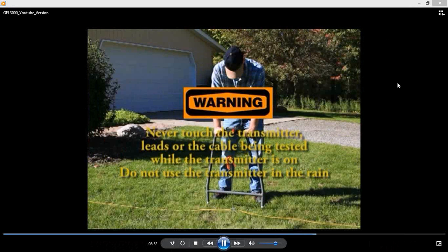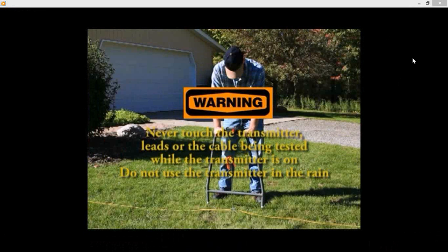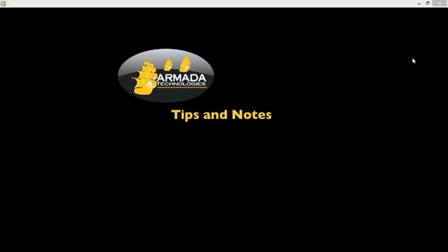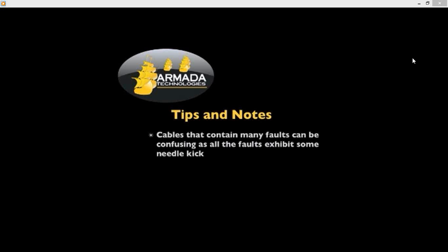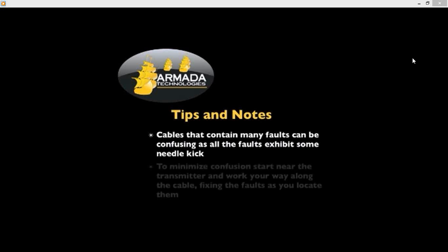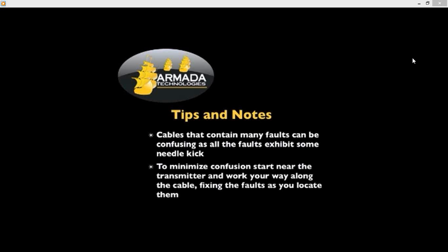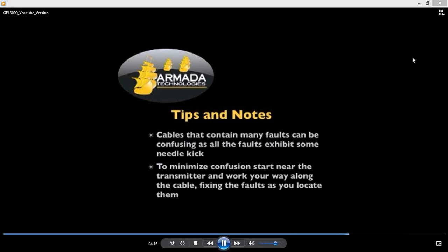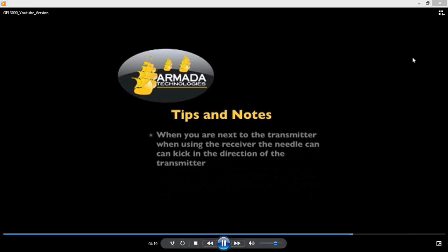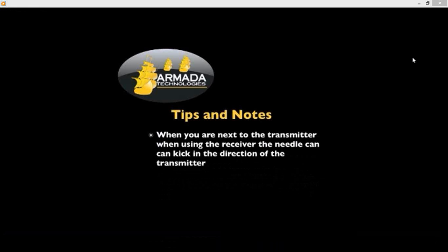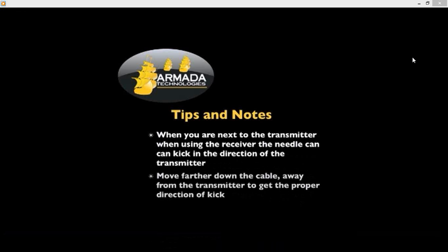Before repair, turn off the transmitter and disconnect it from the cable. Never touch the transmitter, leads, or the cable being tested while the transmitter is on, and do not use the transmitter in the rain. Failure to follow these precautions could lead to injury or death. Cables that contain many faults can be confusing as all the faults exhibit some needle kick. To minimize confusion, start near the transmitter and work your way along the cable, fixing the faults as you locate them. If you are next to the transmitter when using the receiver, the needle can kick in the direction of the transmitter. Move further down the cable, away from the transmitter to get the proper direction of kick.